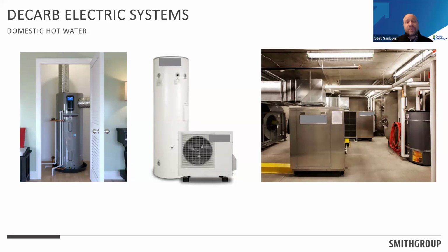I don't personally recommend putting them in a small closet without having the air supply ducted in and out, because the closet will get very cold. Even when it's louvered, there's a risk of subcooling that closet and going into electric resistance mode, which you don't want to have happen.